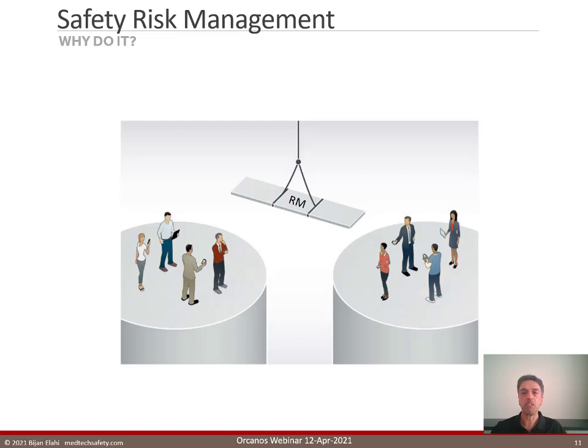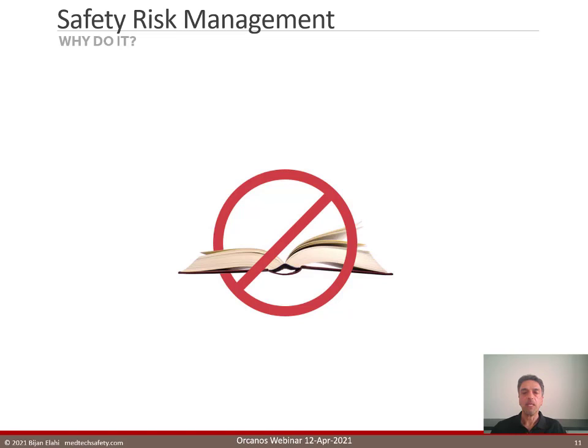Risk management, because of its multidisciplinary nature, requires people of various teams to talk to each other. This brings real value to the company by discovering mistakes early and fixing them. Even though risk management produces a risk management report, which is mandatory to get regulatory approval, the purpose of the risk management process should not be to produce a report, but to influence the design of the system to ensure that it is inherently more safe when it enters the market.